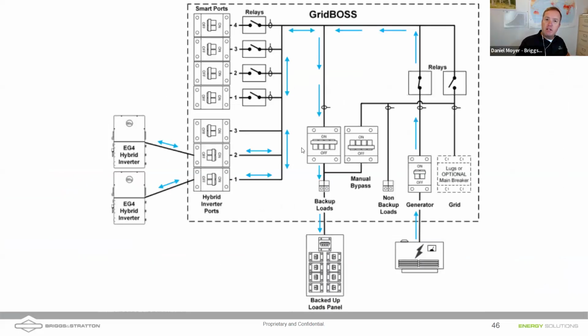So remember that example of the generator running? The generator started up because the grid's down and the batteries are low. We're going to feed generator power up. The grid's down, that relay opened up, generator power comes up, goes down and backs up all the loads. The generator power now flows down into our FlexBoss inverters and starts charging up our Briggs Stratton batteries.